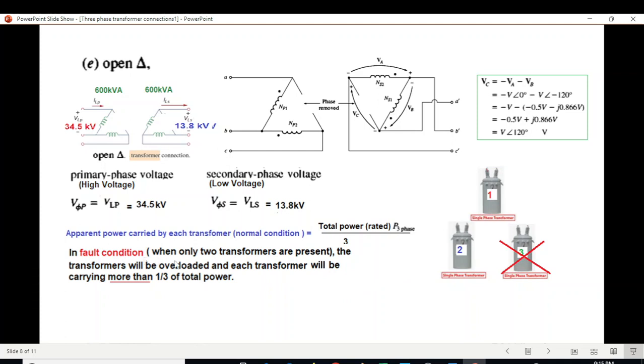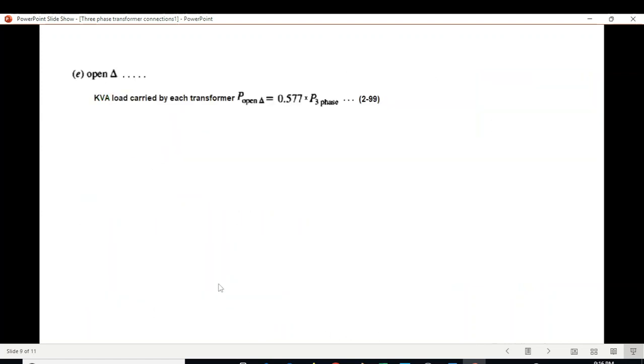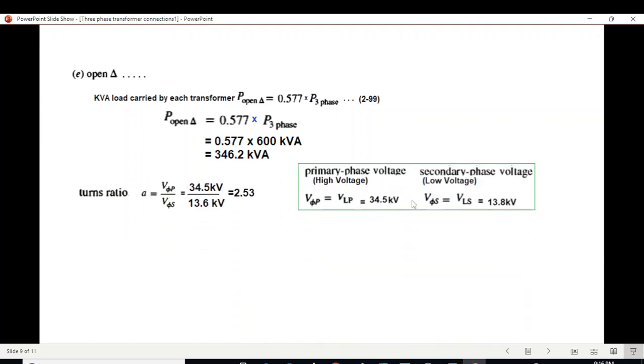For apparent power, we need to consider that in fault condition when only two transformers are present, the transformers will be overloaded and each transformer will be carrying more than one-third of the total power. The formula is: load carried by each transformer equals 0.577 multiplied by the three-phase total power which is 600. So we calculate 0.577 times 600 kVA gives us 346.2 kVA for each transformer. We can calculate turn ratio using the V_primary and V_secondary we already calculated.